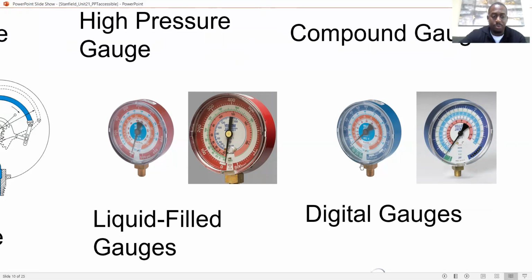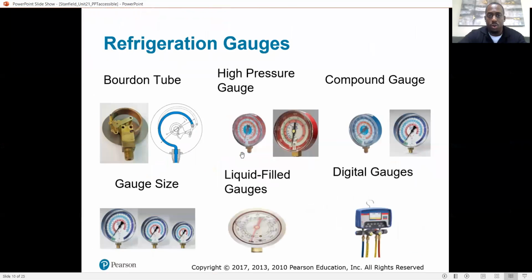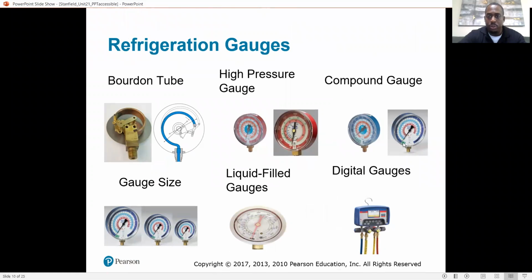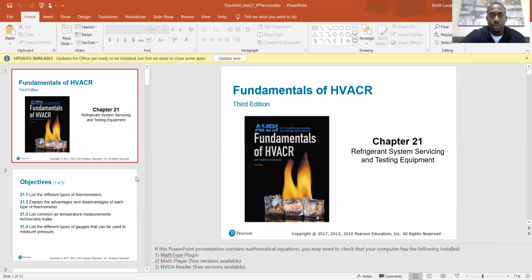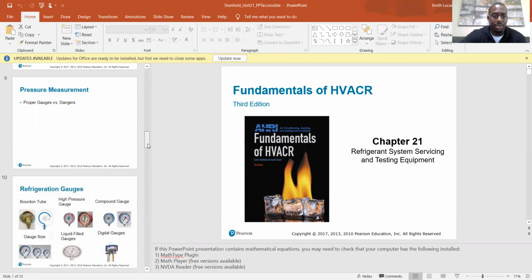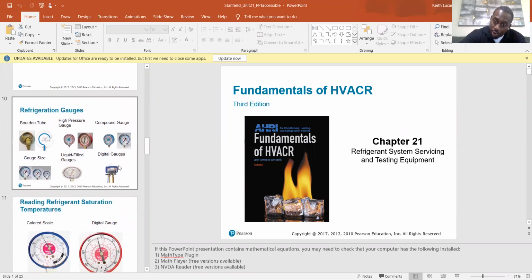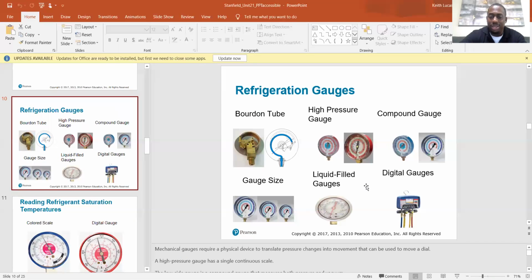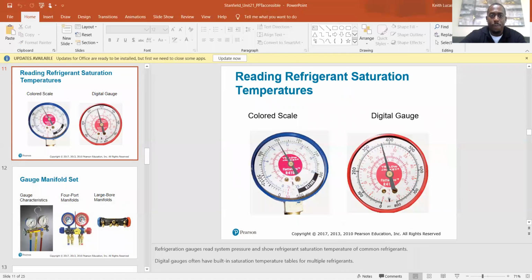Although that's not what you want to go by, because it doesn't go as low as you want. It only reads inches of mercury. And we want to get down into microns, which is why we don't measure our vacuums with our compound gauge. We get a separate micron gauge. Or if you got digital gauges, it's a micron gauge built in. So again, it's like a whole tool bag in one tool.